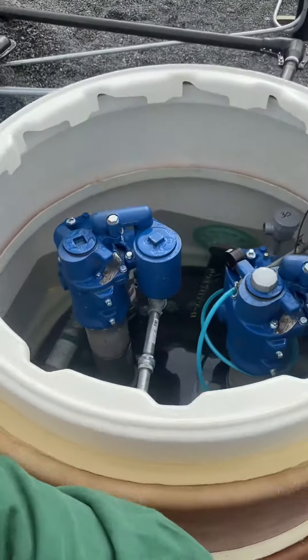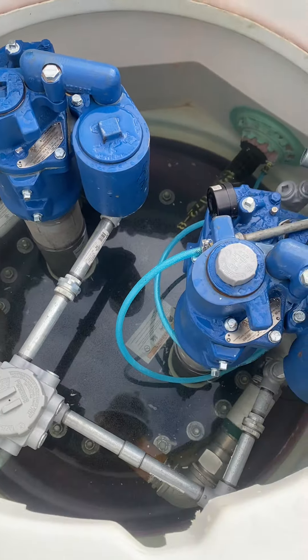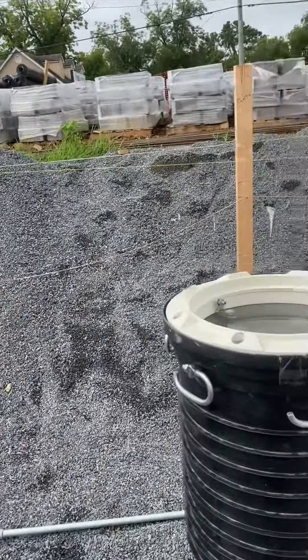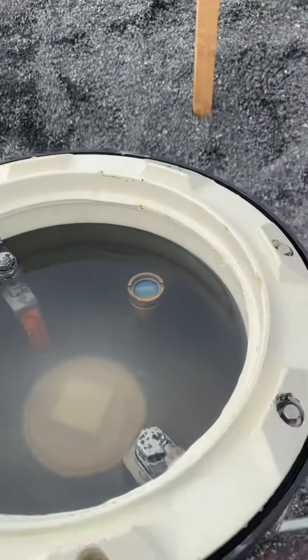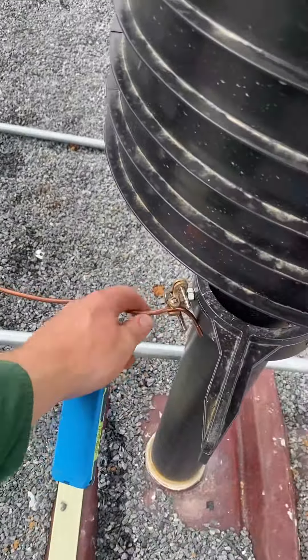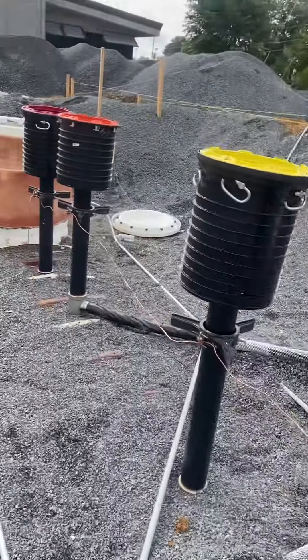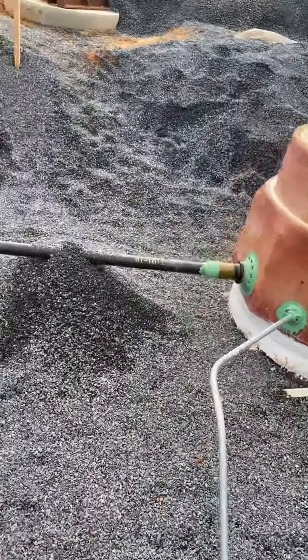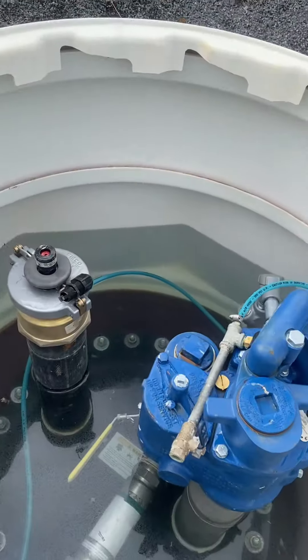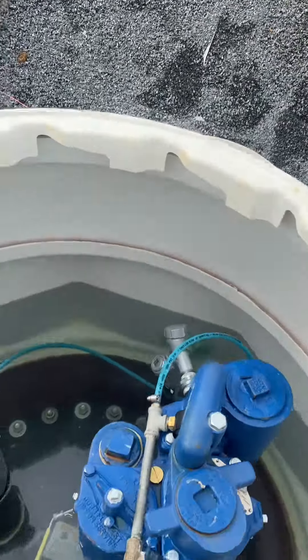Water test on all your equipment — any kind of electrical has an explosion proof fitting and seal. Separate ground for your pumping stations and where they're filling for trucks. Water test on it — I want you to see ground wire tied, coming in to your separate ground rod, not to your service ground rod but a separate ground rod. Water test on all your fittings, making sure nothing's leaking, and again, anything electrical has got an explosion proof seal and fitting.